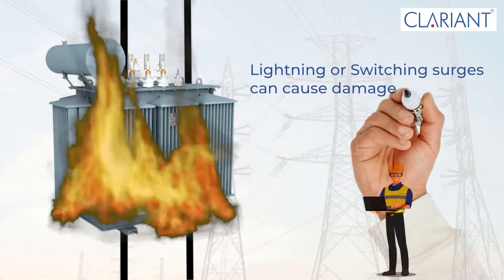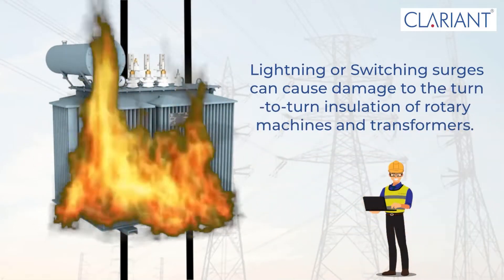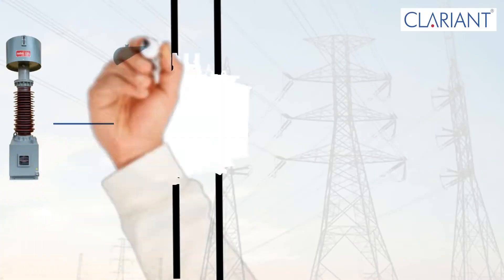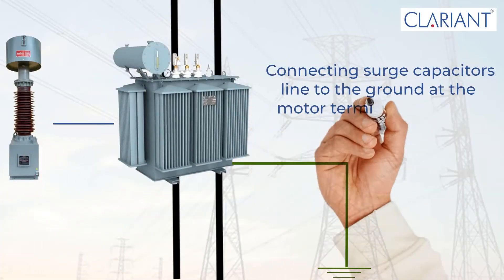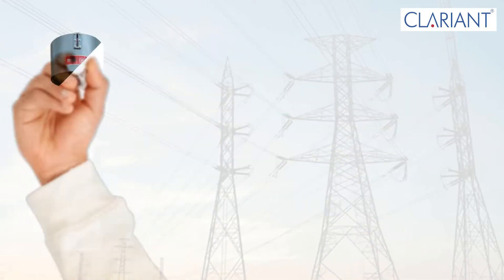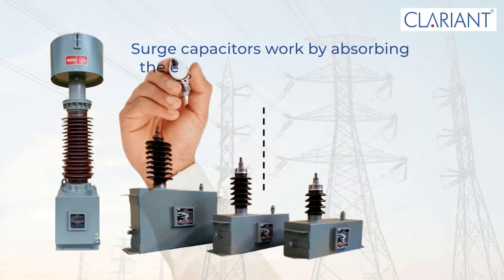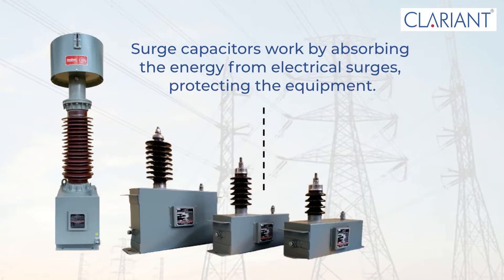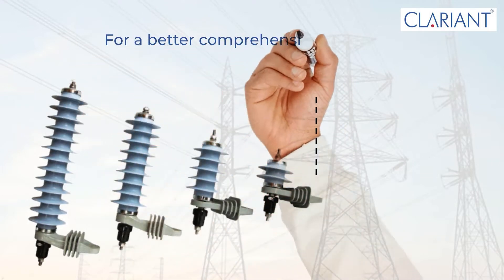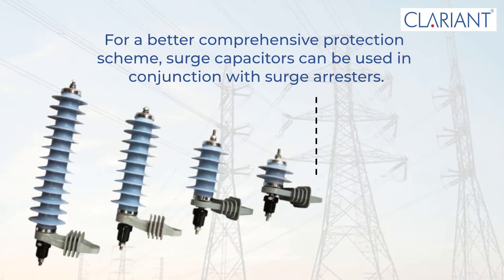Lightning or switching surges can cause damage to the turn-to-turn insulation of rotary machines and transformers. Connecting surge capacitors line to the ground at the motor terminals prevents this damage. Surge capacitors work by absorbing the energy from electrical surges, protecting the equipment. For a better comprehensive protection scheme, surge capacitors can be used in conjunction with surge arrestors.